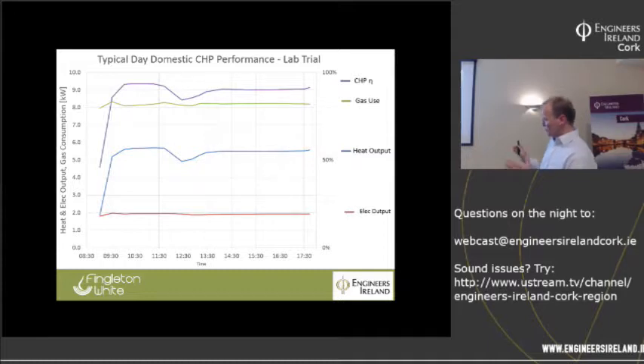So if we take that particular day, the electrical efficiency was 23.5%, the heating efficiency was 66%, and the average overall efficiency for the day was 89.4%. Putting those figures into the previous calculation, primary energy savings are 21.5%, and that's the equivalent of what we get in an industrial gas turbine CHP. It's substantial savings, and really the question is, why aren't we selling more of them, or any of them?